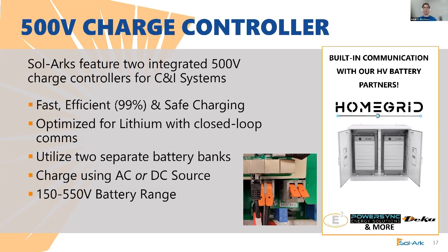Lithium communications only. You cannot use any battery bank that you want. We do have some high voltage battery partners that you can look up on our website. We will recommend HomeGrid definitely, and we're working on those communications. So you're going to be able to utilize 2 separate battery banks, as I mentioned, and charge using an AC source, such as the grid or a generator, or the DC source, which will be the solar panels on the roof. For the 30K, we do have a 150 to 550 volt battery range, and it will increase for the 60K.